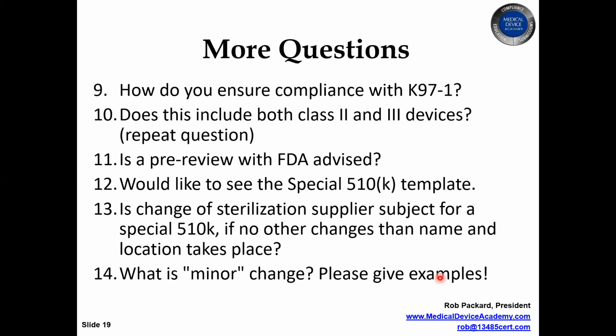Next on the list, is change of sterilization supplier subject for a special 510K? If you're changing the supplier, no. You would change your registration and listing. So you would list, or the supplier would be listing differently. They would list your device instead of the old supplier listing your device. And you can have more than one sterilization supplier if you wish.